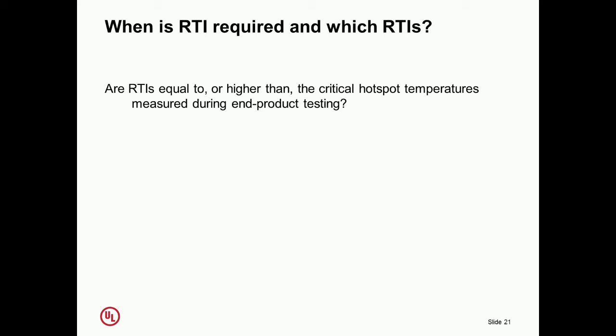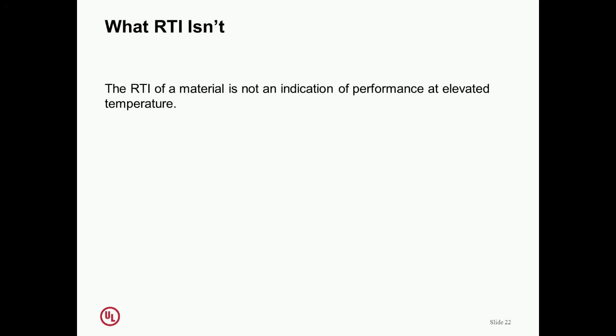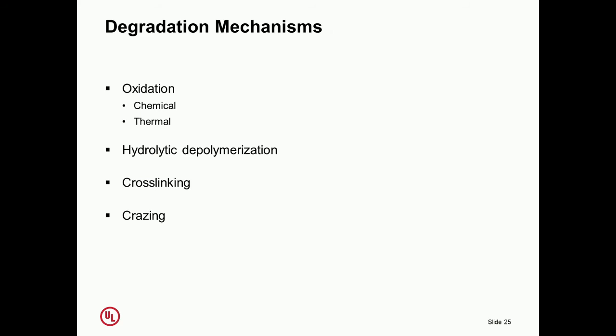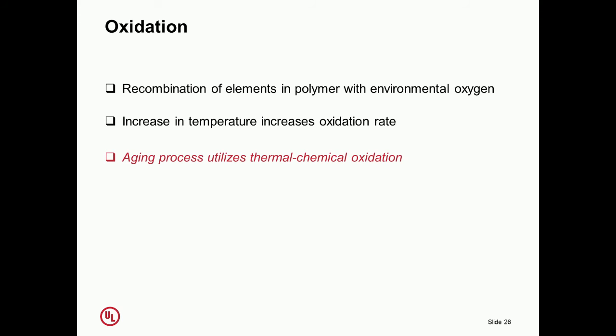If the RTI or relative thermal index is higher than the normalized hottest temperatures, or what we call sometimes worst case temperatures during normal use, then we consider it to be suitable. But again, it's not an indicator of performance at elevated temperature at all, it's just showing that it maintains its characteristics. A lot of materials will have generic RTIs based on a lot of field experience, and many will have that relative thermal index identified through testing. Let's talk quickly about the degradation mechanisms. We have oxidation whether chemical or thermal, hydrolytic depolymerization, cross-linking, crazing, etc., with polymer materials.